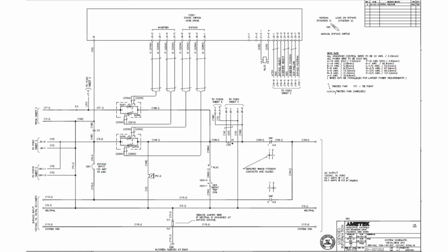Now, if we need to do some maintenance inside the UPS or a repair or something like that, in many cases, we want to shut down the UPS and we want to get into what we call manual bypass or maintenance bypass. So what we do in this circumstance is, and every procedure on the front of our UPS systems will tell you to do this first, transfer the system to bypass using the static switch. So remember, this is the static switch. So you would press the bypass to load button on the front of the UPS, and that would switch off the inverter static switch.